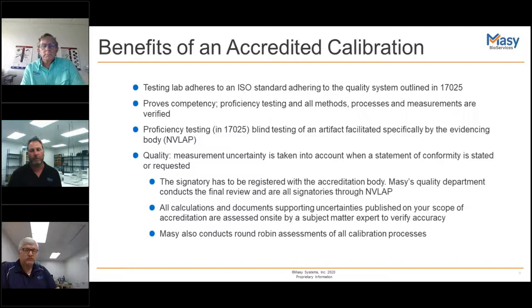Proficiency testing is a big part of the quality system for measurement. It's essentially a blind test of an artifact, facilitated by NVLAP, interlaboratory programs, or another accreditation body. They send in an artifact, whether it's an SPRT or a weight set, and challenge that device against our best capabilities.